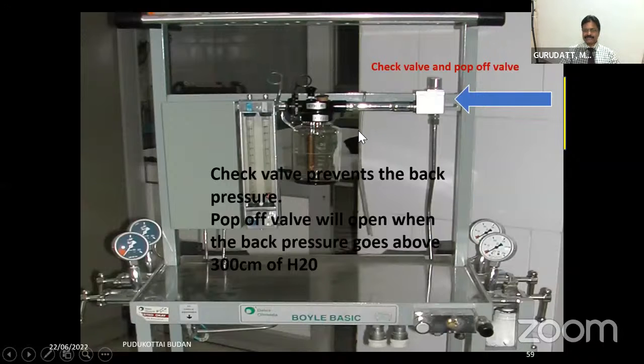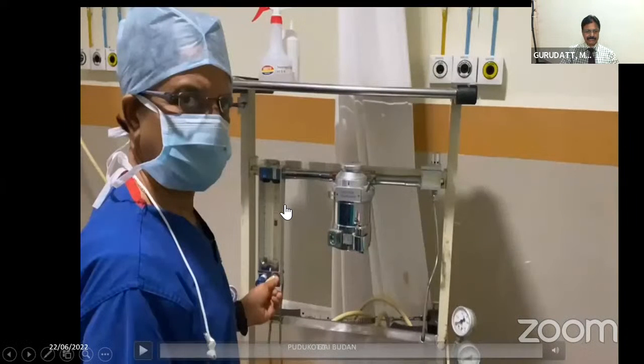In order to prevent this pumping effect and pressurizing effect, we have the check valve, which will prevent the gases from flowing back towards the flow meters and the vaporizers. And also we have a pop-off valve. This pop-off valve will open once there is a sudden increase in the pressure to more than 300 centimeters of water pressure. So I'll show you one of the videos of how this pop-off valve works.